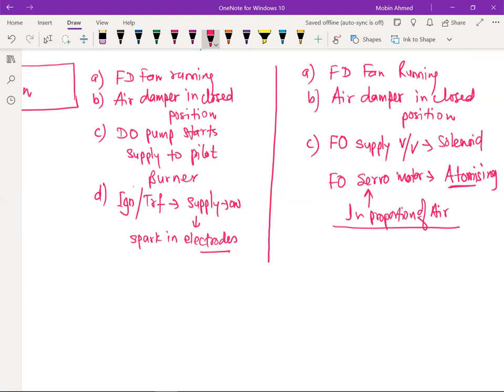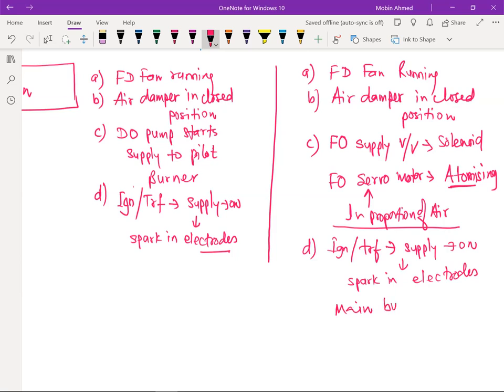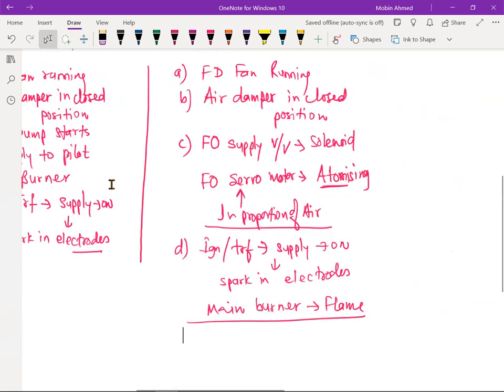So it is going to atomize, and the ignition remains the same here. So the ignition transformer gets supply, so the spark is available in the electrodes. Spark in electrodes. Now here in this case, the main burner is going to have the flame. Main burner is going to have the flame. Okay. The oil flow and all this, if you have worked in Aalborg, you will come to know. But I need to tell you a little bit if you have any confusion.